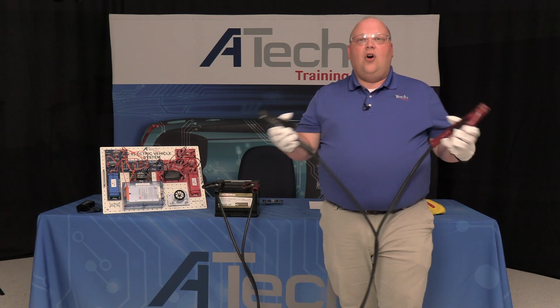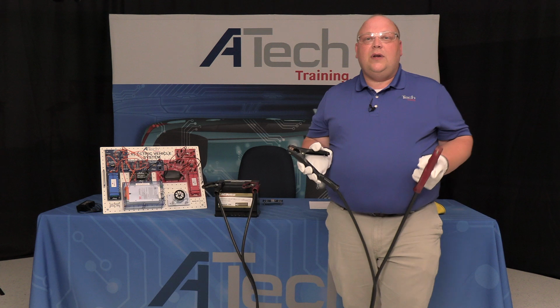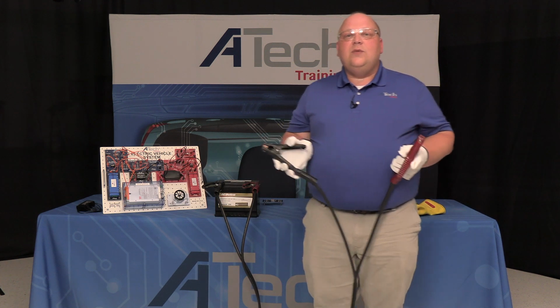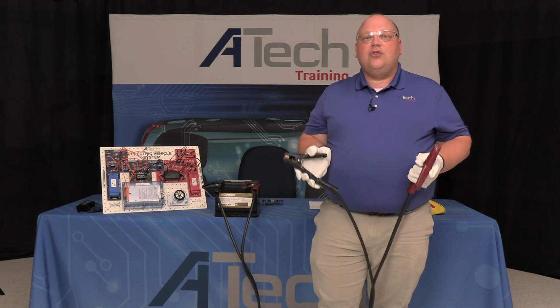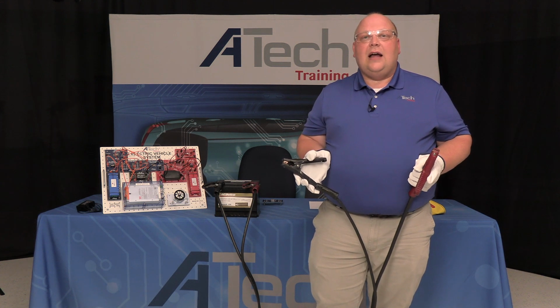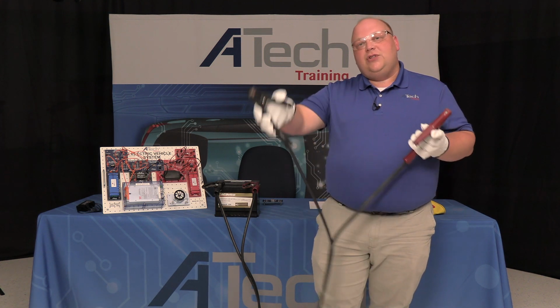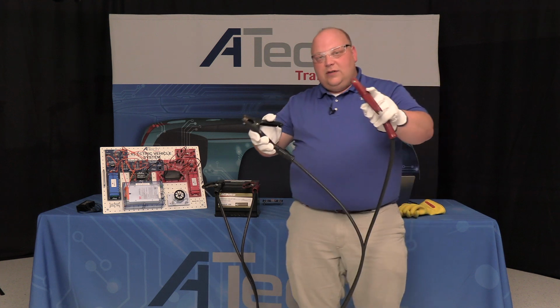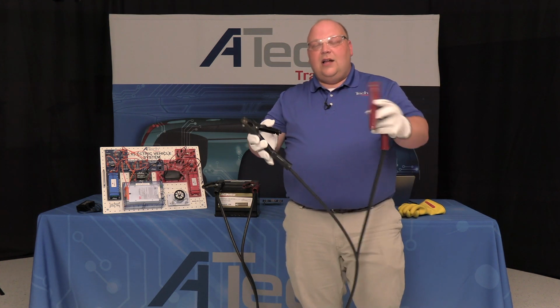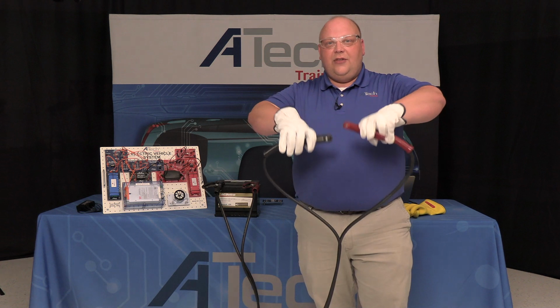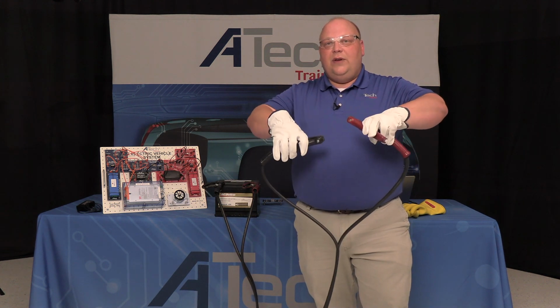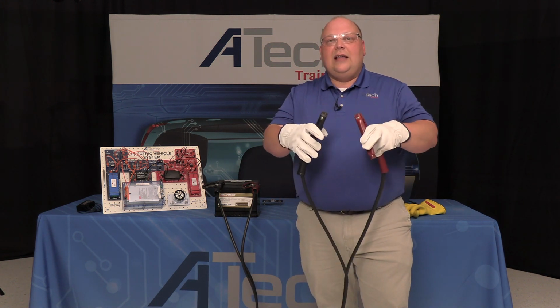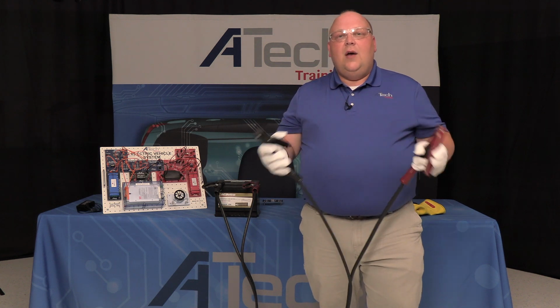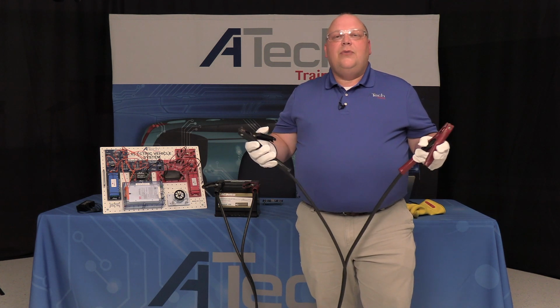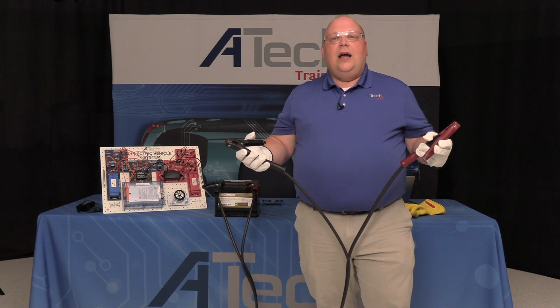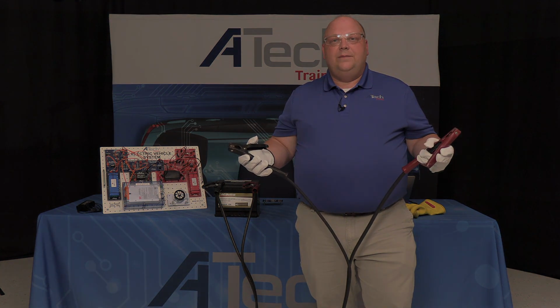Okay, so we get a lot of arcing, we get some smoke coming off here, we get a lot of heat generated, and the reason why we have to have that pre-charge relay built into the contactor is so we can supply voltage to the ground side as well as have the voltage on the power side, so when we bring both of these units together, there's not a difference of voltage from either side. When we do that, we don't get that arcing, we don't get that heat buildup, and we don't get that smoke that comes through the process of bringing two high current, high voltage wires together.